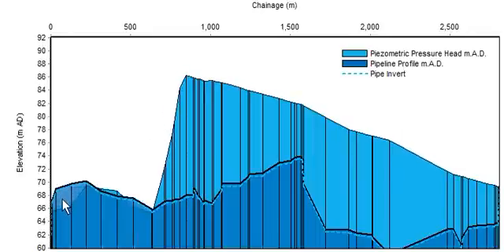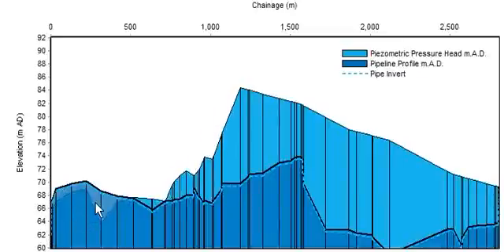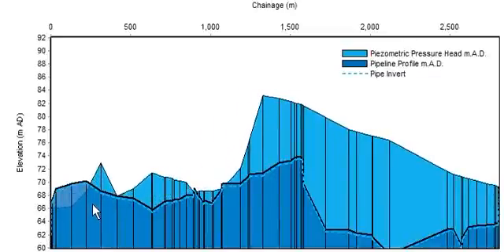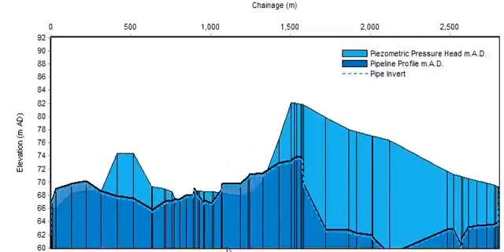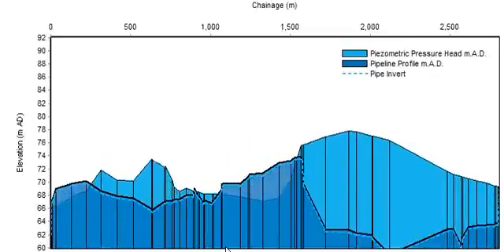If the pressure drops sub-atmospheric, air comes into the pipeline. If it goes down to minus 10 meters, we get vapor pressure forming in the pipeline, which can have drastic events.